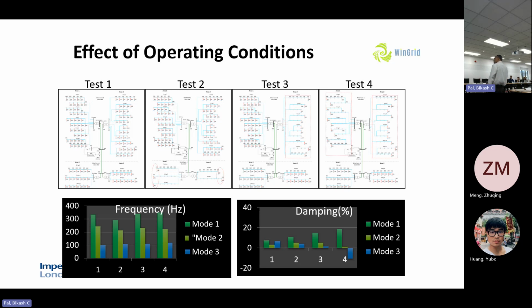This is the frequency of those 3 modes, and this is the damping of those 3 modes for test cases 1, 2, 3, and 4. One can see that for test case 4, when many turbines on the upper part of the wind farm are down, we now have an unstable situation because the damping is negative.